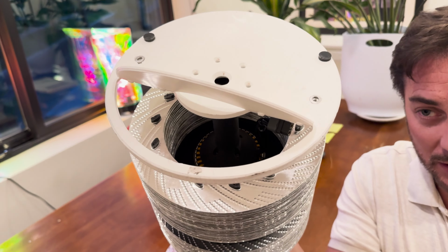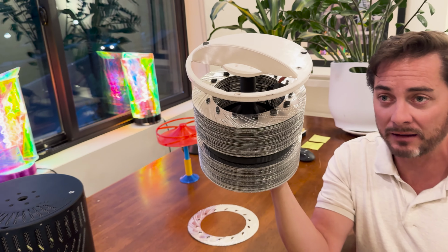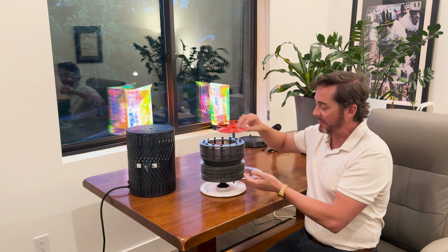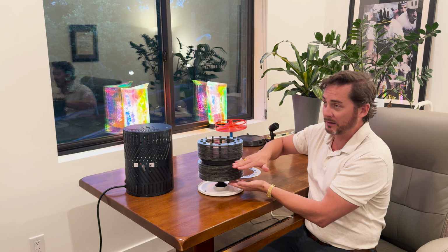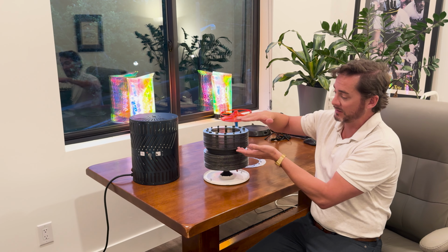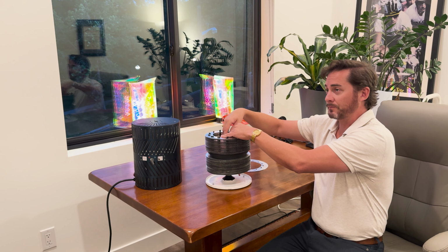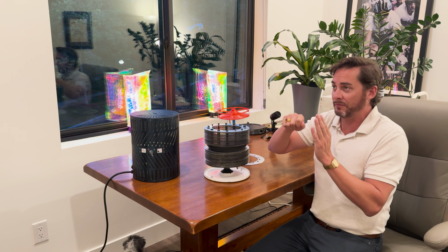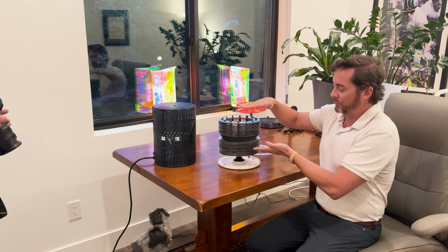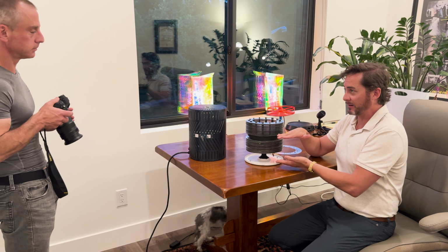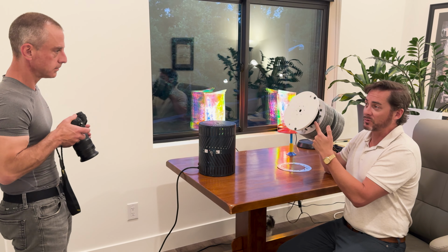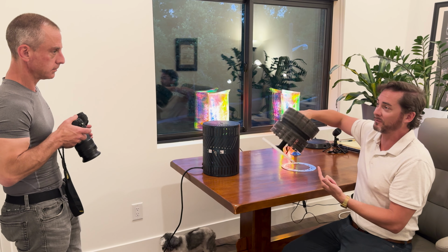And brushless DC motors enjoy being modulated at high efficiency. So we only need one motor, and that runs this fan section, which in a typical air conditioner would be a different motor. It runs this fan section, and then it runs the compressor. They all work off that same motor. In a typical air conditioner, you can't modulate it down. You can modulate the fan down, but we're able to modulate the entire system down, which means, because the motor sits in an air inlet, we're able to overdrive it to 130% for 3 minutes.